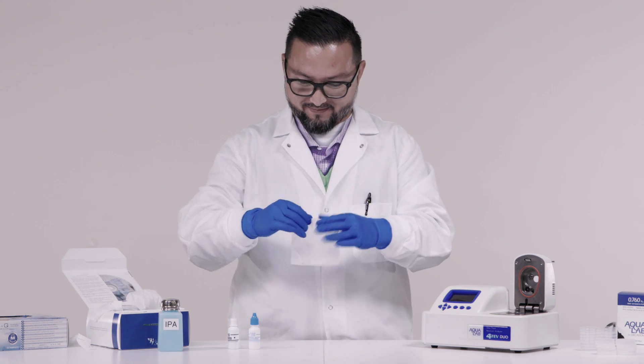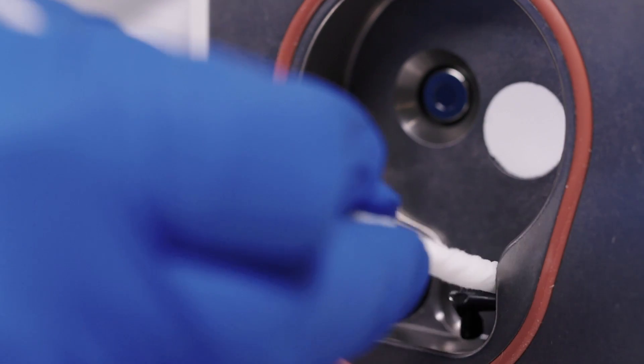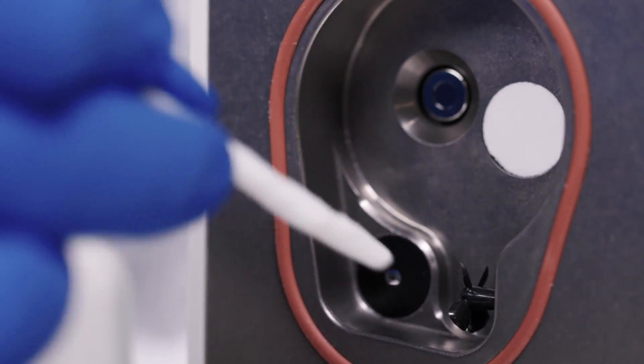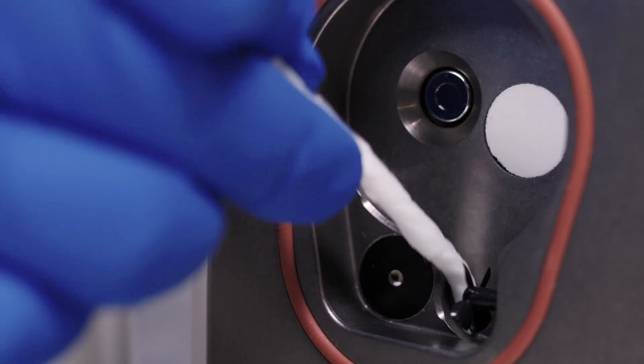Repeating the same clean, rinse, dry process used to clean the sample chamber, wash, rinse, and dry around the fan and the sensors in the upper block. Now that the block surfaces are clean, it's time to clean the sensors.